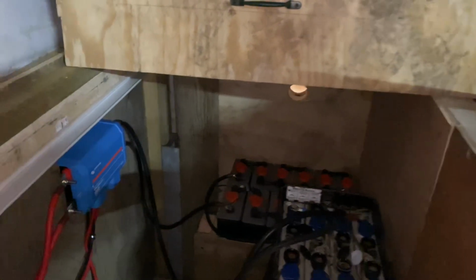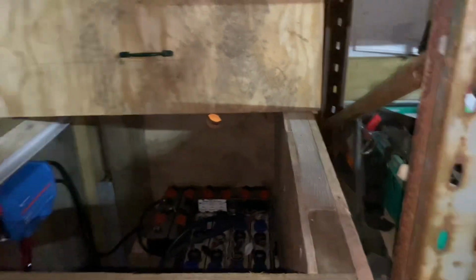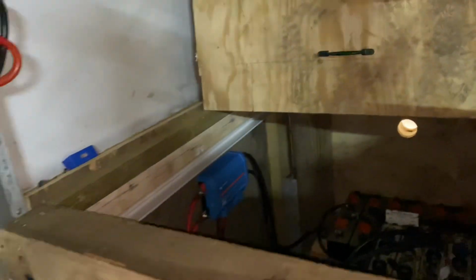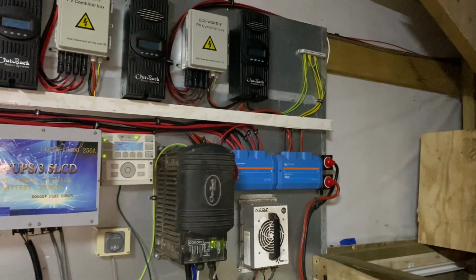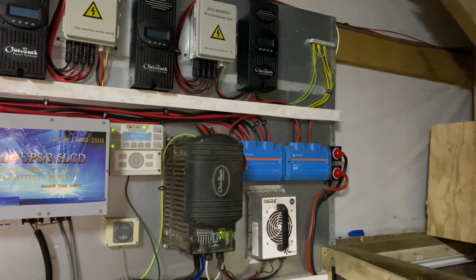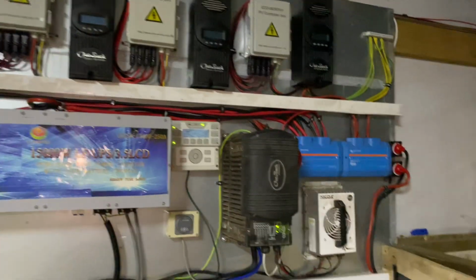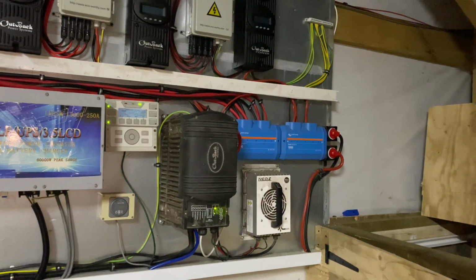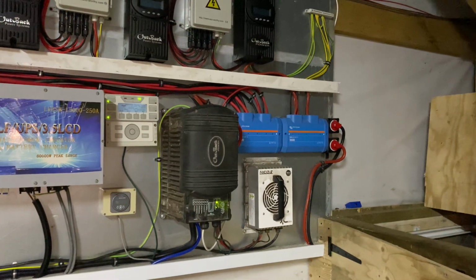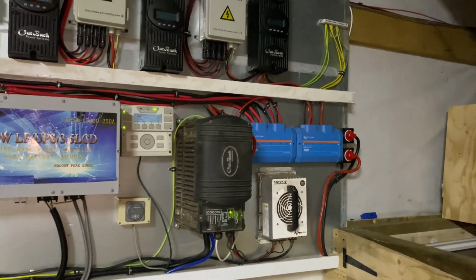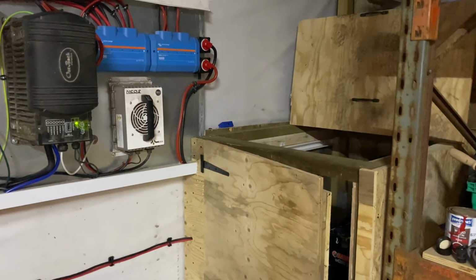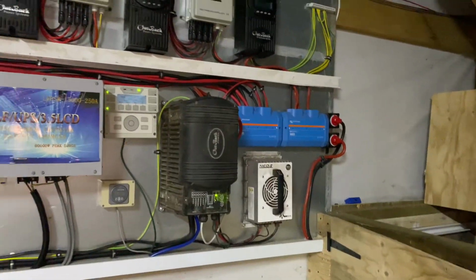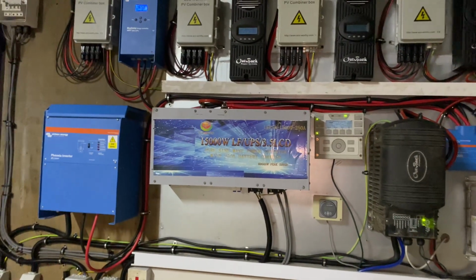So that's basically our system. At the moment we've got 12.8 kilowatt of solar panels. We've got way too many solar panels, but solar's cheap and it's more for in the winter. You know, solar panels in the winter only put about 5% of the rated capacity out. So 12 kilowatt will still get probably 600 watts on the worst day, which should be enough just to keep everything going. And hopefully we'll get through the winter without running the diesel generator.